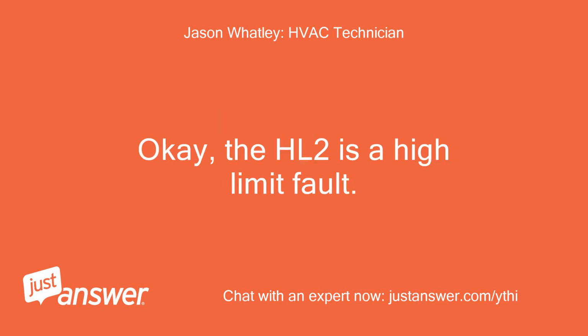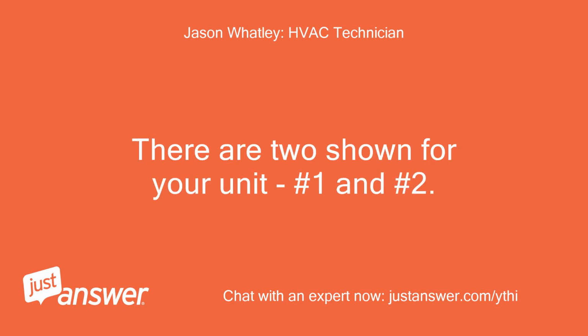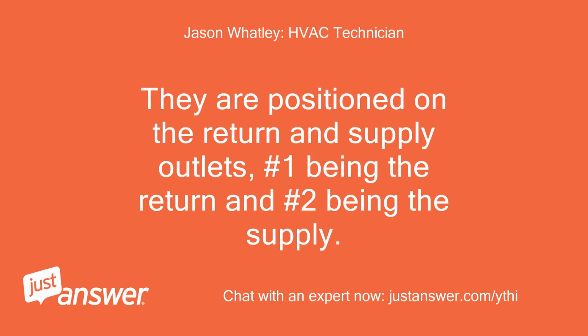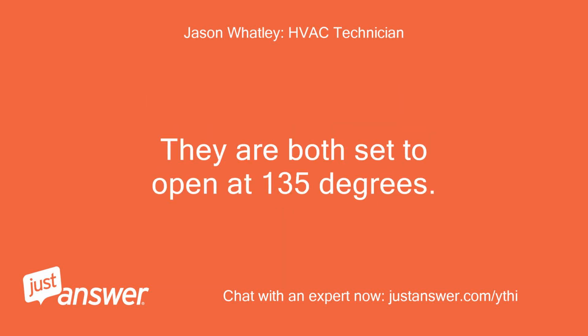Okay, the HL2 is a high limit fault. There are two shown for your unit, number 1 and number 2. They are positioned on the return and supply outlets, number 1 being the return and number 2 being the supply. They are both set to open at 135 degrees.